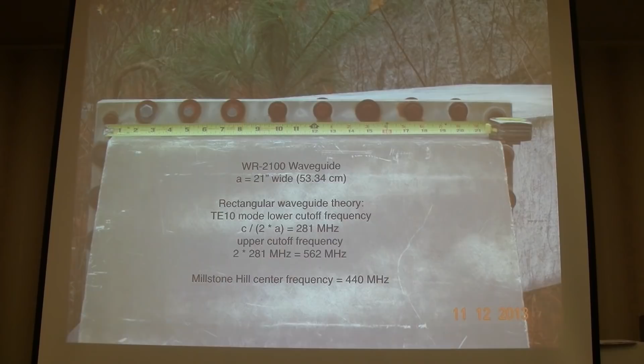And you all remember your TE10 mode cutoff frequency, don't you, for rectangular waveguides? So the bottom cutoff is 281 megahertz, and the top is 562, and I use it at 440, so I'm right in the middle of the transmission frequency path. And it's got very, very low loss. I don't remember the number, but if we switch back to English units, per 100 feet, it's in the 0.05 dB range, or somewhere in that range, because you've got a lot of metal.